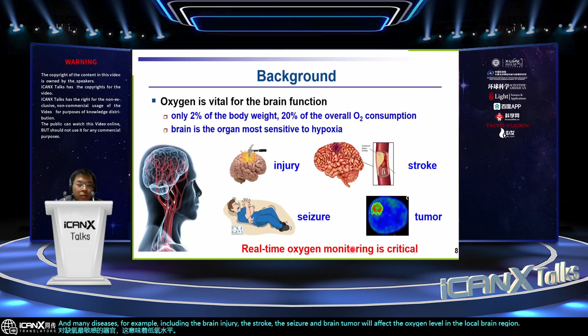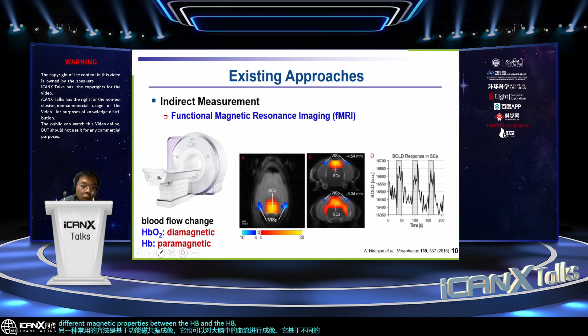There are some existing technologies for oxygen detection in the body. For example, the measurement of blood oxygen saturation. We are very familiar with the finger clip pulse oximeter. This detection is based on the optical absorption difference between oxygenated and deoxygenated hemoglobin, the Hb and the HbO2, in the red and near infrared regime. Actually, this is an indirect measurement because it only detects the hemoglobin, not the oxygen molecule. Another commonly used approach is based on functional MRI, which can also image the blood flow in the brain. It is based on the different magnetic properties between Hb and HbO2. So this is also an indirect measurement of oxygen.